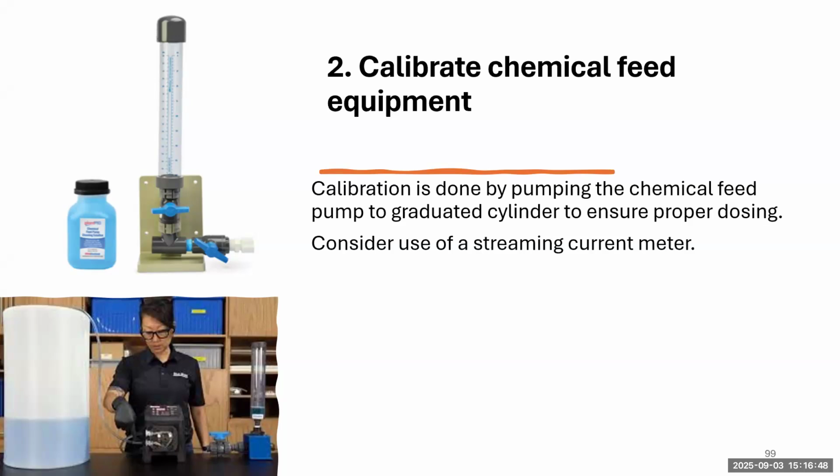So you see the images on the left, the female operator that's testing. She has a calibration tool on the right of that image, and she has a source of liquid that she's running through that metering pump, and she's trying to see, is the dosage accurate and consistent. And you can see one of the devices on the top left of the screen, a graduated tube that you can use to measure the dose that's being delivered.